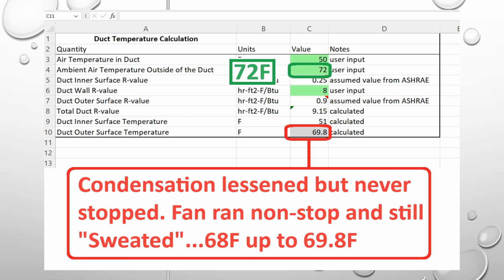So this is the exact same formula that we ran before. Here's our 50 degree supply air. Here's a 72 degree ambient, which is 2 degrees higher. And here's our R8, and our duct outer surface temperature was 69.8. So we raised it a good couple degrees, but it was still running the fan all the time. So unless you want to run a fan underneath your crawl space 24/7, I don't advise using this solution.